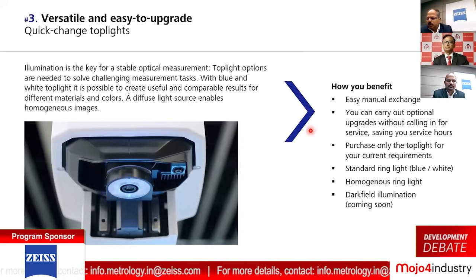All of you must be knowing that any optical measuring instruments normally have at least two illuminations. One is light coming from the bottom, what we call transmitted light, and one is light through the optics, what we call coaxial. But in addition to these two, we always have a ring illumination.